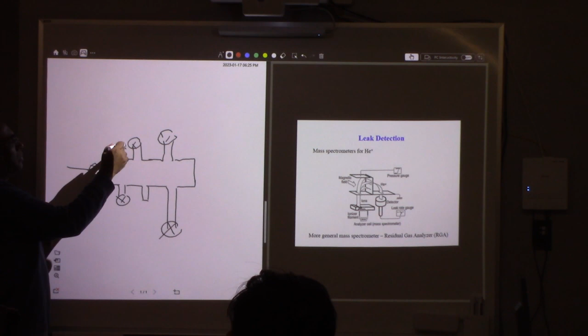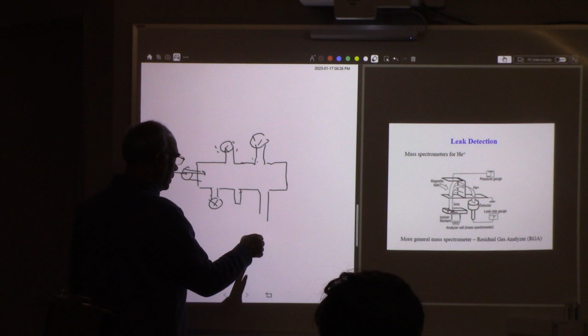If it is a tiny leak, you cannot get to the lowest pressure, but it's very difficult to see where the leak is. In that case, you have to use something called a leak detector, using a mass spectrometer, like a helium mass spectrometer. What we do is, you just pump the system. Then I connect this one to my pump, and I just pump the system.